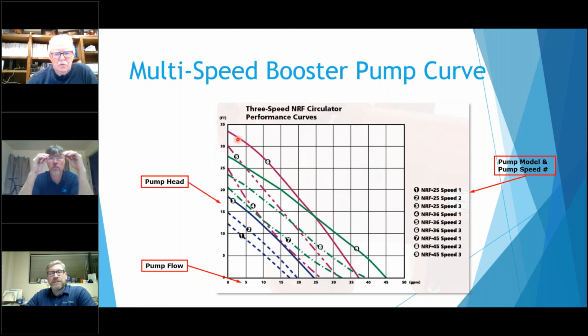Now you got these, I don't know if you can see it, but they're kind of color coded. You got red or a burgundy color for this number 6 there, so it's the NRF 36. The green is the NRF 45. And this blue is the NRF 25. So depending on what speed setting you have and what pump you have is what curve you're actually going to read for this one.